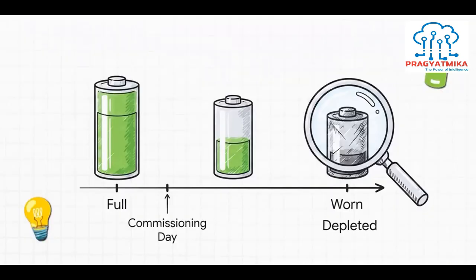The takeaway here is absolutely crucial. Your system has to be mathematically designed to perform on its last day of life, not just commissioning day. Imagine a commercial frequency regulation system that perfectly hits its targets on day 1, but then falls short and breaches its contract in year 5 just because of standard expected degradation. That is an engineered failure.